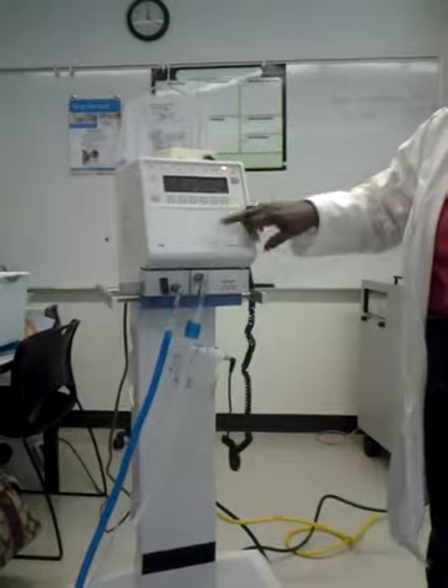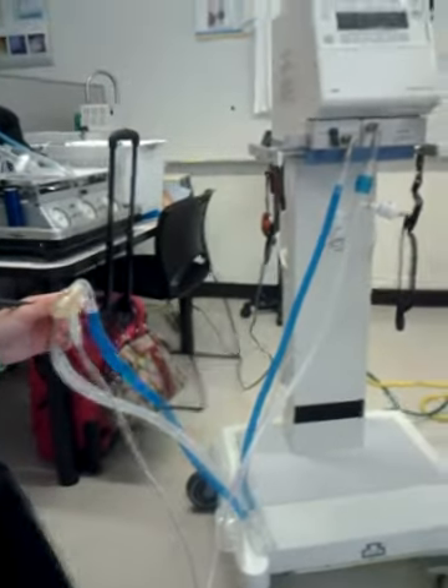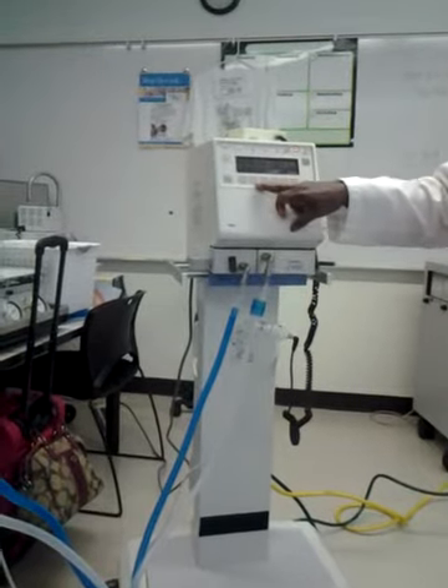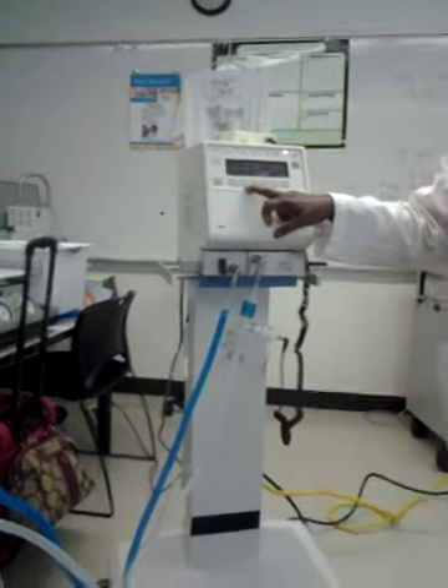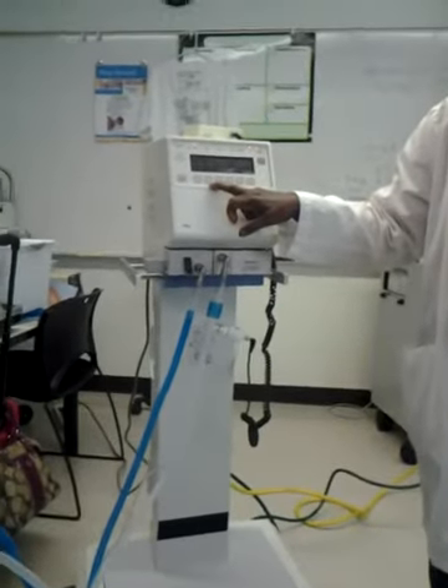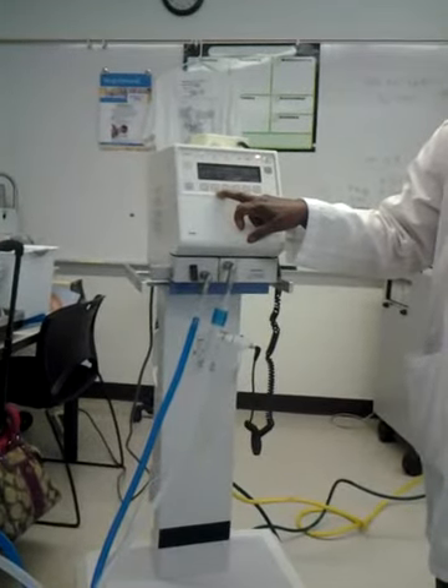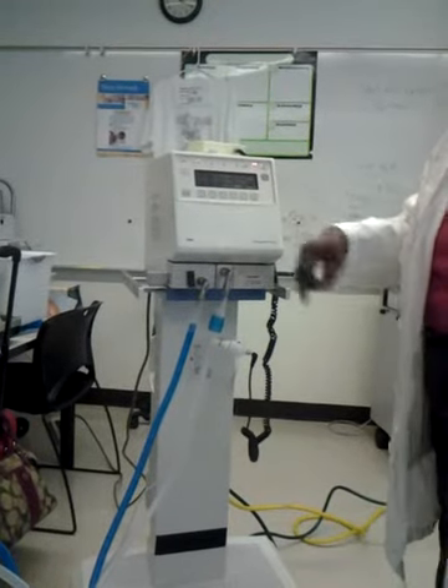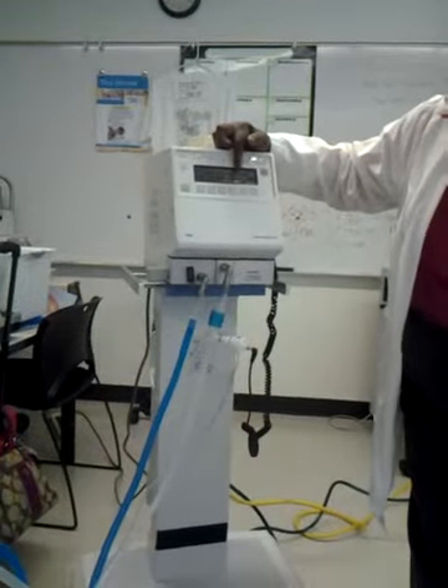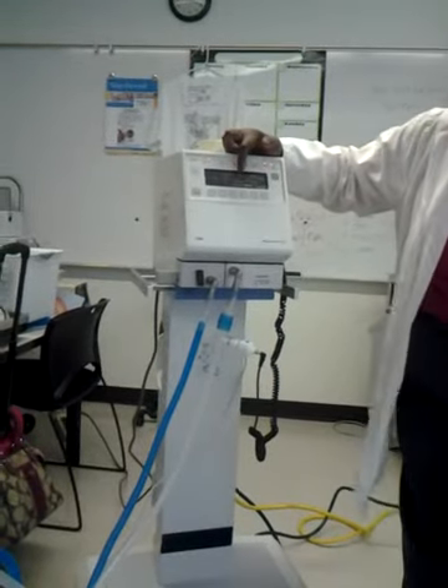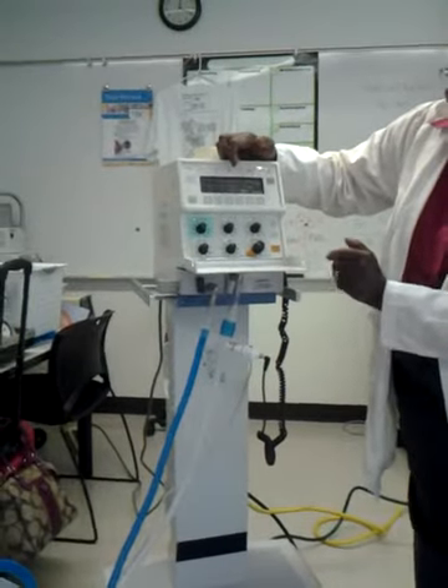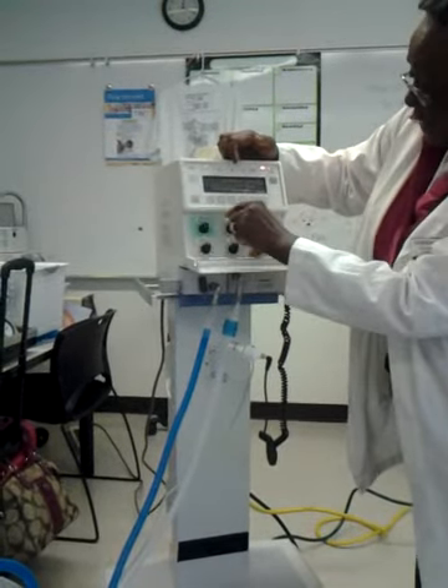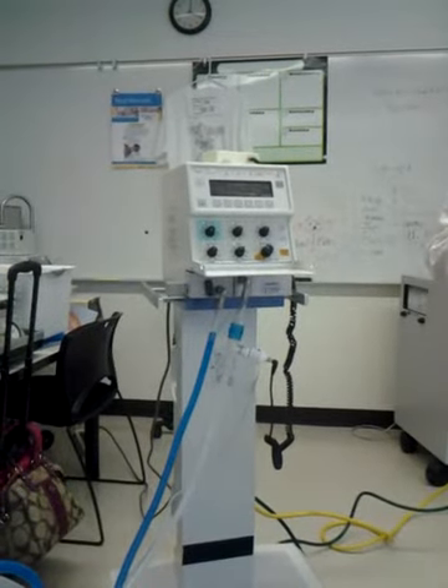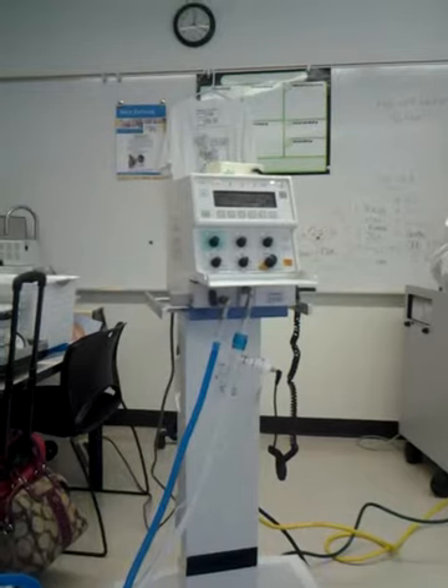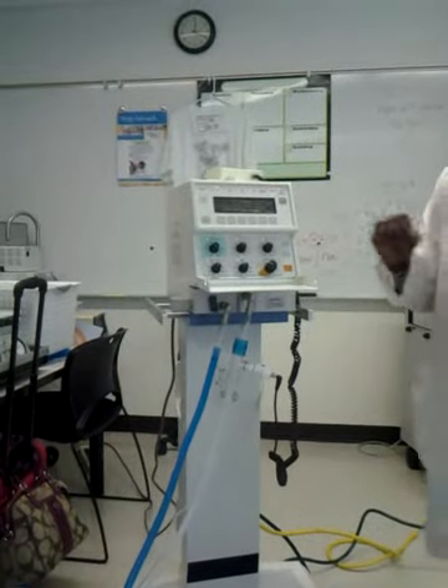Okay, so if I want to put my patient on assist control, which I just did, now I can give the patient volume guarantee, pressure control ventilation, but it's giving me volume guarantee. That's kind of like PRVC for an infant. When I said that, you see I have my tidal volume here that I can turn on. And down here I would set my peak flow, my FiO2. Now one thing I like about this machine, you don't set a rate specifically. You set an I time and an E time, and that gives you your rate.